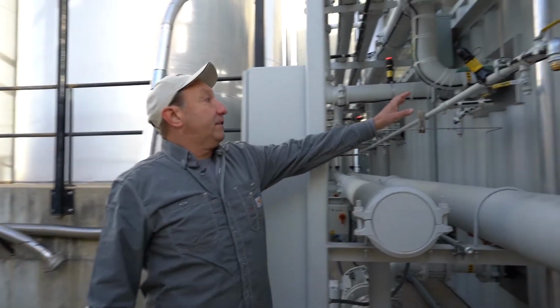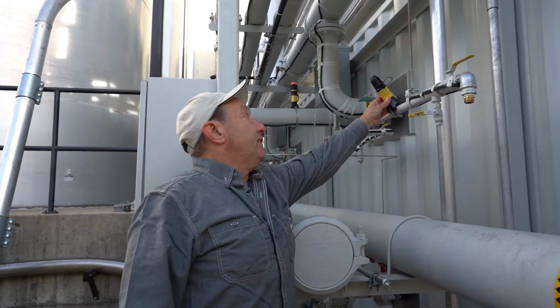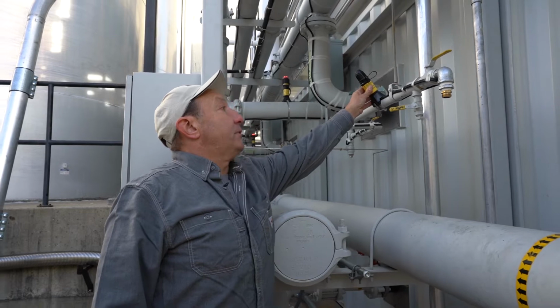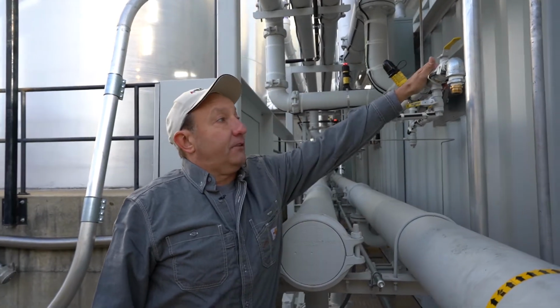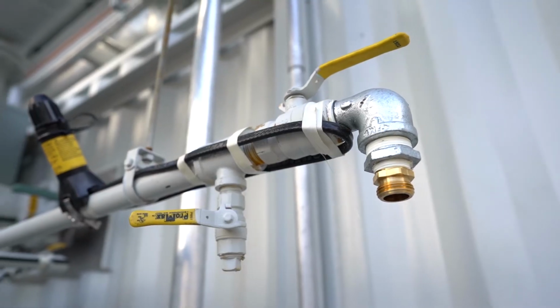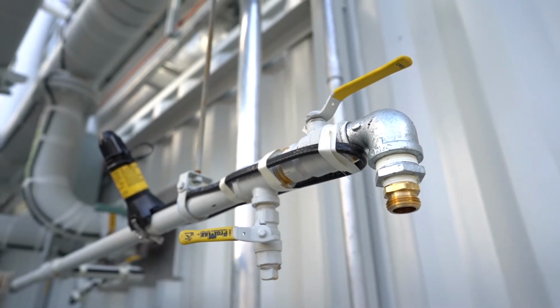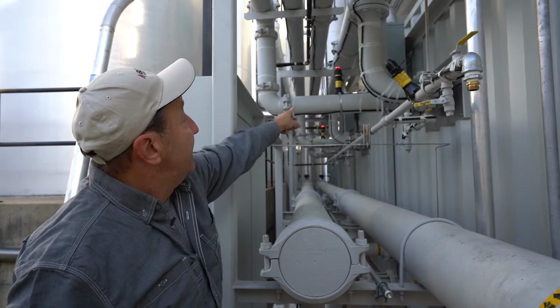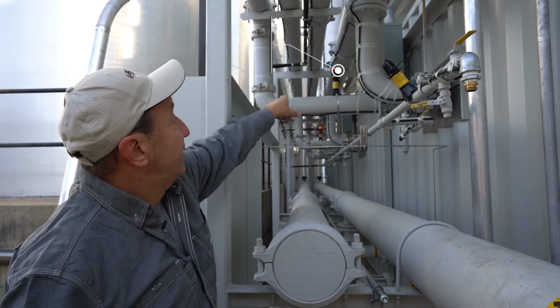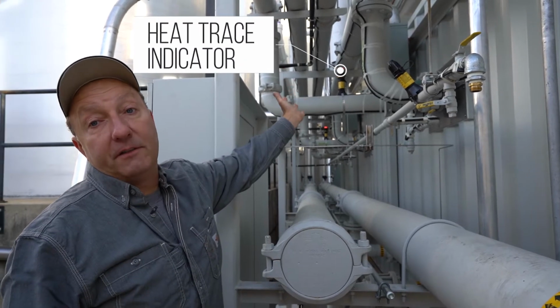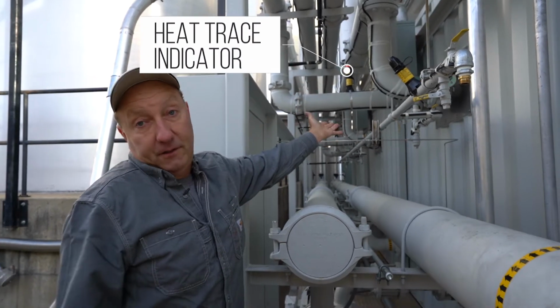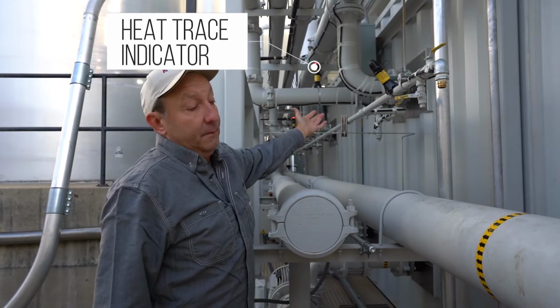Right here, this is another example of the heat trace. This is one of the end caps. This is the heat trace. I can actually feel that it's warm. They are on and being utilized right now. They're just not covered in insulation. Then you can see the indicator at the other end of the heat trace has a light saying that it is powered, it's energized. If the light is off, the heat trace is not energized.